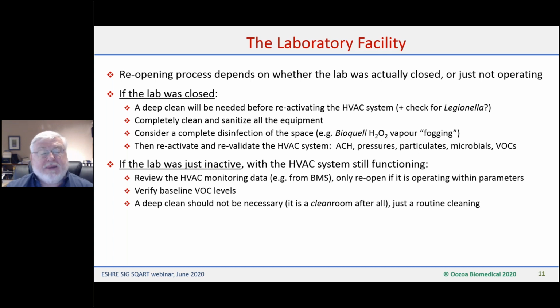If you just made the lab inactive and left the HVAC system still functioning, then you just need to review the HVAC monitoring data, for example from your building management system, and you can then reopen the space if the HVAC is operating within expected parameters. I would still recommend verifying the baseline VOC levels, especially if you're doing a lot of restocking with fresh consumables. A deep clean should not be necessary because it's a clean room after all, so it should still be clean if the HVAC's been functioning and no one's been in there - you might just need to do a routine clean down.